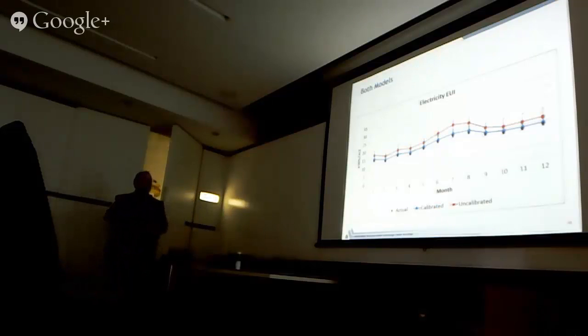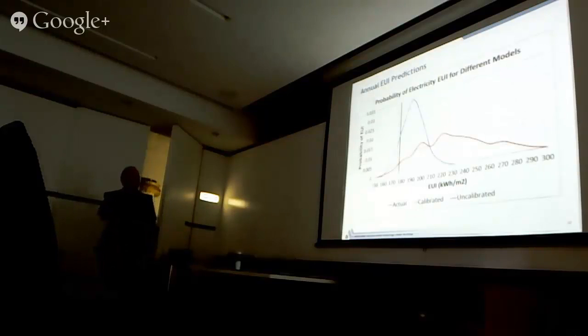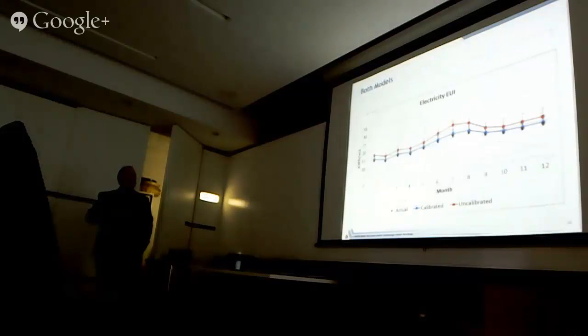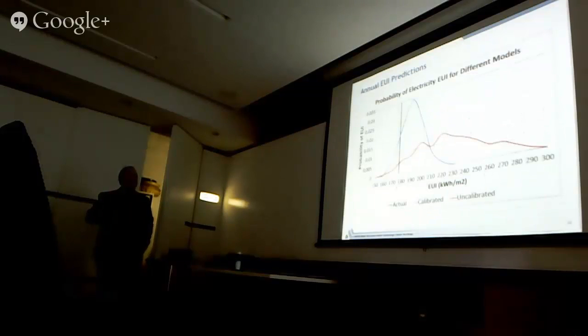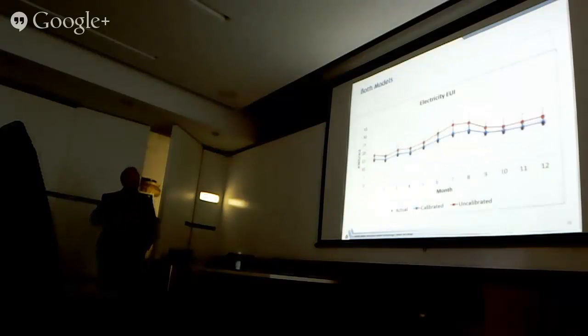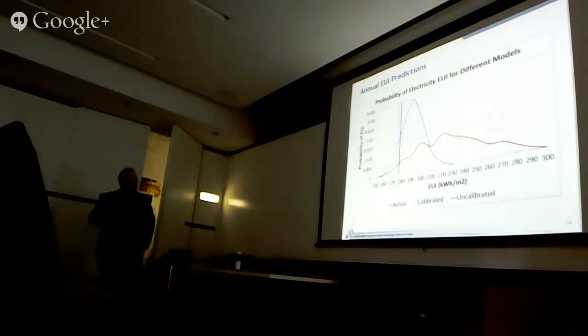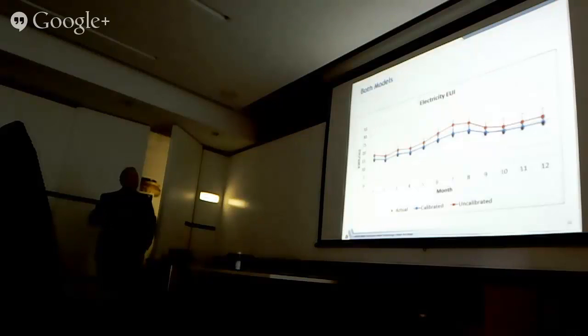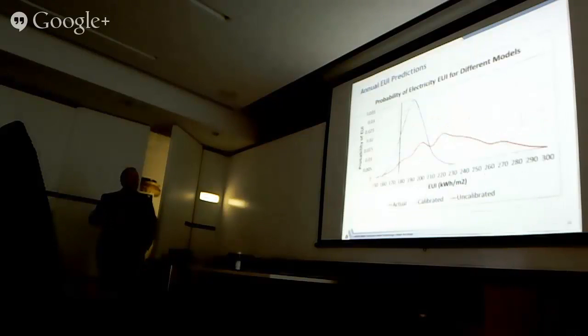So here's our uncalibrated and our calibrated on one plot. This is our month by month. Usually when we're done, we actually want our single number at the end. This is an idea of the probability distribution that we would get out of these models, calibrated and uncalibrated. This black bar is the actual energy use, the EUI for the year. I added up each of those months and get 178, 177. This red, even though month by month it looks really small, actually has quite a high annual EUI when you add them all up.